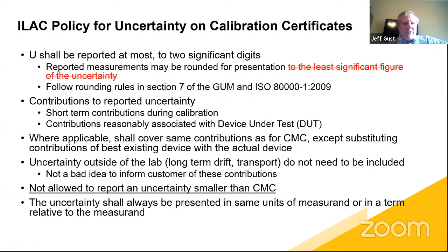The contributions to the reported uncertainty: you have the short-term contributions during calibration and contributions reasonably associated with the device under test. Where applicable, you need to cover the same contributions as you did in the CMC, but you don't have to add to the CMC. You can substitute that contributor out of the CMC for what you're actually doing in your actual device as well. So you don't have to double count things. The uncertainties that occur outside of the laboratory, like long-term drift or transport, don't need to be a part of your uncertainty. But it's not a bad idea to inform your customers that you could have these.